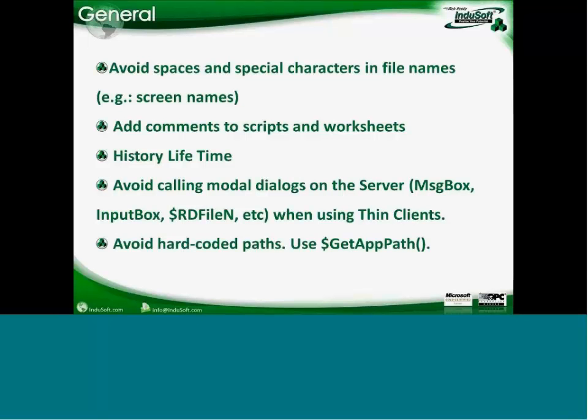So we recommend avoiding using functions that open dialogues like message box on the server, because when you have thin clients, if you press a button on the thin client and this button calls a function on the server, in a script that is executed on the server, the message box or the dialogue will be displayed on the server, not on the thin client.